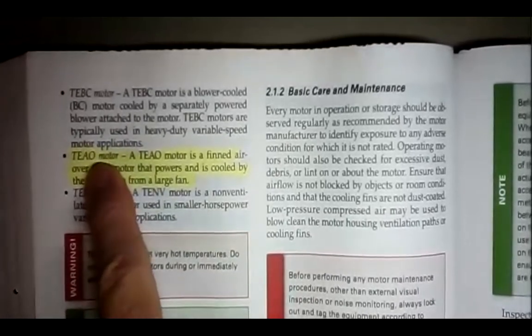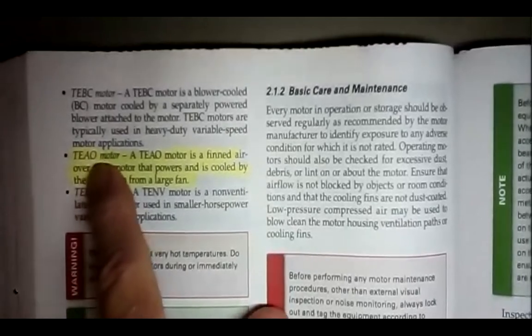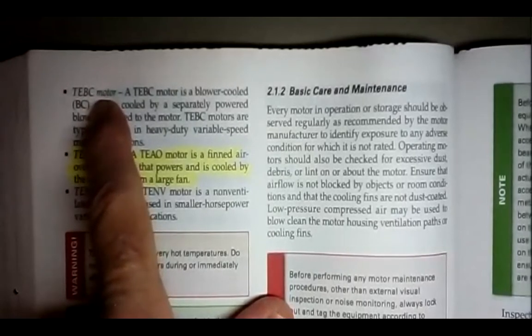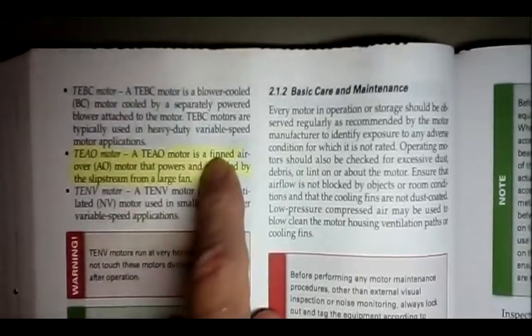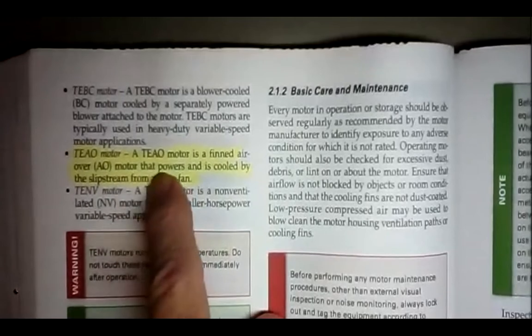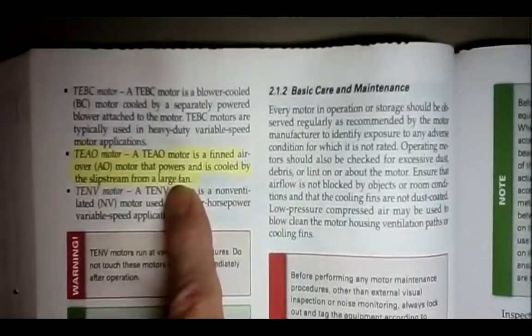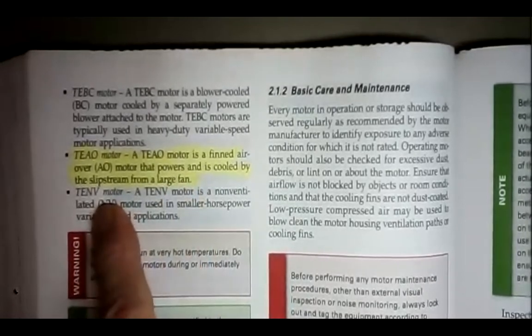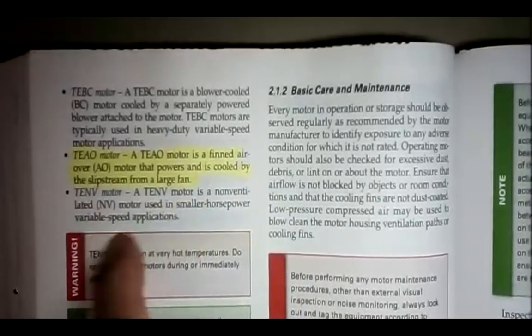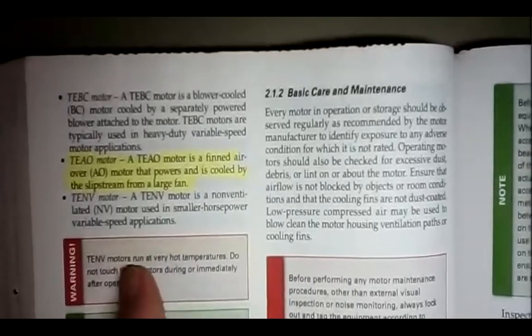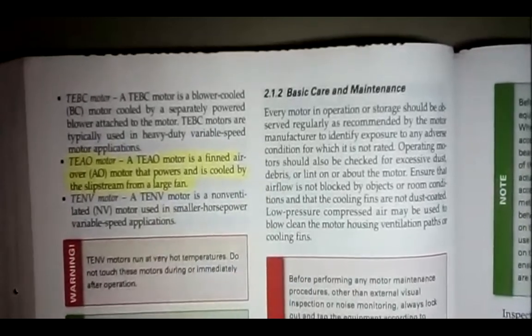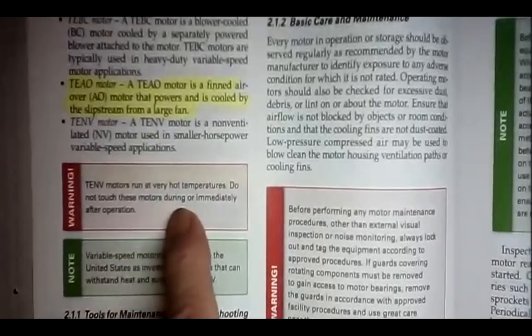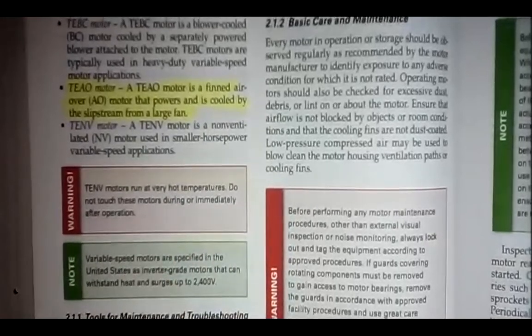These are different types of motors. The AO is air over. They're cooled by air over. This is blower cooled. TEBC motor is a blower cooled motor. A TEAO motor is fin. It's a finned air over motor that powers and is cooled by the slipstream of a large fan. So on the rotating shaft of the motor, they actually put a fan with fins that blows air over the motor and cools the motor as it operates. And this is a non-ventilated motor. TENV, non-ventilated. TENV, non-ventilated motors run at very hot temperatures. Do not touch these motors during or immediately after operation. They're hot enough they can burn you.